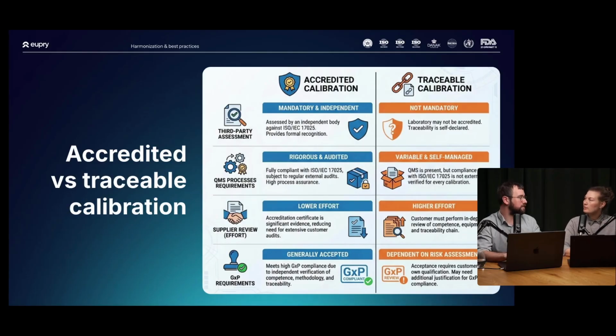So how do you see this from your calibration certificate? Well, all of the accreditation bodies will have an accreditation logo that you are only allowed to use if you are an accredited company. And often you will have a calibration number tied to your specific calibration laboratory. So if you don't have that specifically on your certificate, it's most likely not an accredited calibration. And would you also know that they're part of the multilateral agreement by having this? I mean, you need to ensure that the accreditation body who has accredited the laboratory is also part of ILAC. But if you're in Europe or in the US, you're covered.